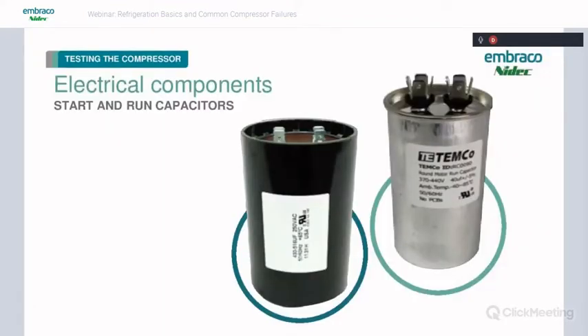Then we have two types of capacitors. We have start and run capacitors. Basically, the start capacitor is not designed to be held in the system, but just for a split second, just on startup. If you get a sticking relay, you're going to burn up that start capacitor very quickly. So if we have a potential relay where the contacts have welded, you can check amp draw on the start winding of the compressor to see if that start winding is being de-energized. And if not, you've got to change the relay, and you're probably going to have to change the start cap too, because they get burned up very quickly. They're only meant to be in the circuit for that split second startup time.